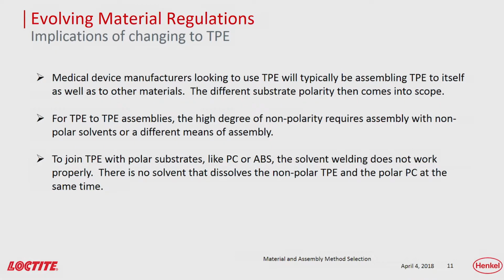So medical device manufacturers looking to use TPE aren't just bonding it to itself. Oftentimes they have to bond to other substrates, and that's where the rub comes in. These different substrates have different polarity, and that can cause issues. So for TPE to TPE assemblies, the high degree of non-polarity requires them to use a non-polar solvent or some other method of assembling those components. However, to join TPE to polar substrates such as polycarbonate and ABS, solvent welding no longer works. So solvent welding is traditionally used for tube set assemblies, but when you have a non-polar going to a polar substrate, there is no solvent out there that will work with both of those. So that's where the challenge comes in.